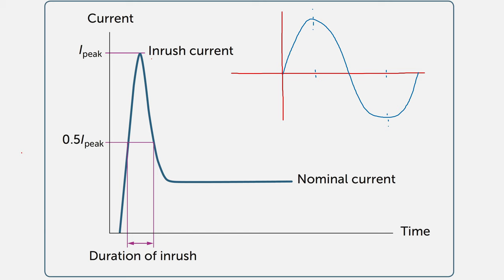Right when a light is turned on we have something called an inrush current — a sudden increase in current versus time. One can see that this increase in current is almost vertical, and that vertical action can initiate a trip on a circuit breaker. Also note that the peak of this current is significantly higher than the nominal current, which refers to the steady-state current.